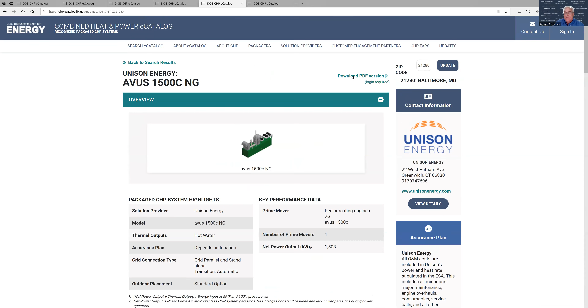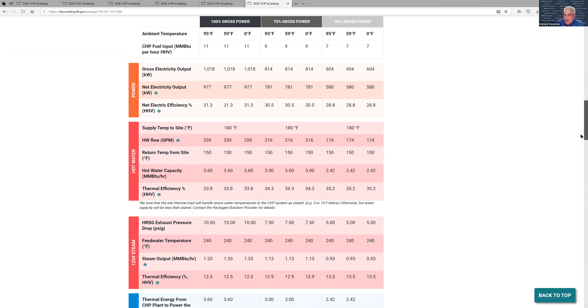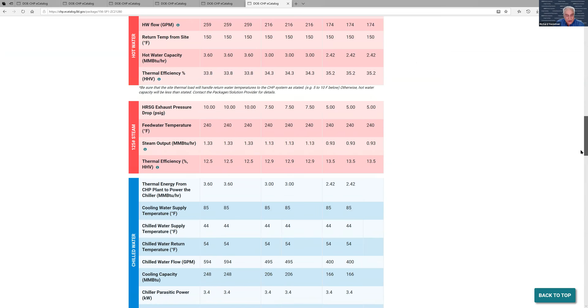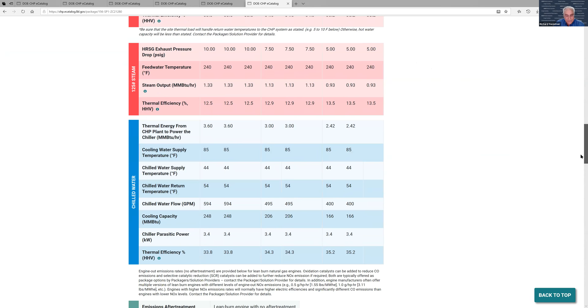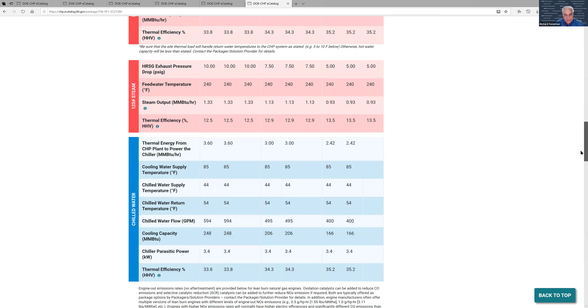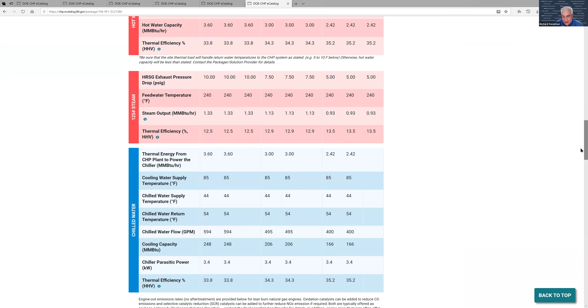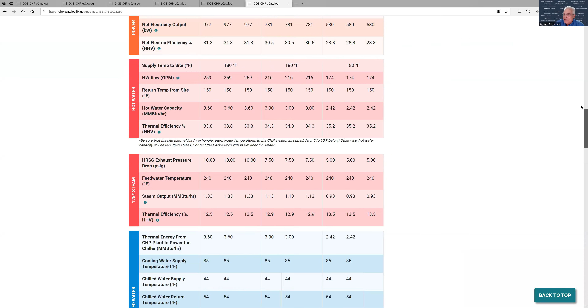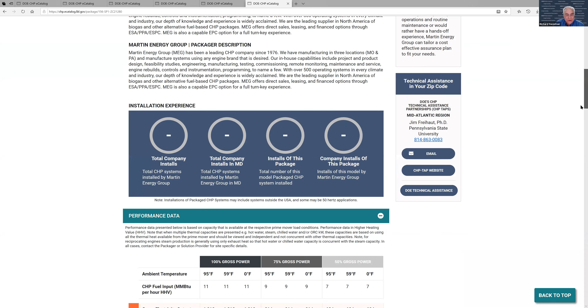Now I do want to show one other thing here. This is a package that has power, hot water again at 180 degrees, steam supply, and also, just below here, chilled water information. In this particular case, as with most engines, this is an engine where the steam is always supplied. The hot water and the chilled water would be supplied - this is at full load capacity - it's one or the other, or a blend of the two. We actually do explain that so we don't get out of balance here, so people understand what that is. And in every case, all you need to do is talk to the manufacturer to get the details.